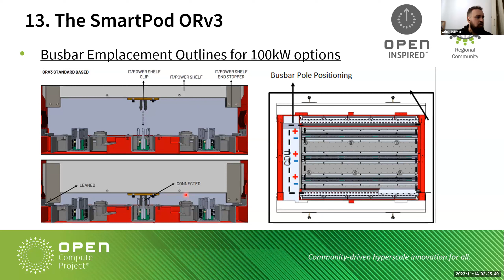This is the ecosystem we designed for the Open Rack version 3. In a SmartPod XL Plus, you can have 100 kilowatts of compute, with 99 nodes of 1 kilowatt each. Then we have the power shelves, each providing 54 kilowatts. With 2 power shelves, you get the entire SmartPod ecosystem at 100 kilowatts of compute. The switches can be placed in the corners here, or outside the tank.